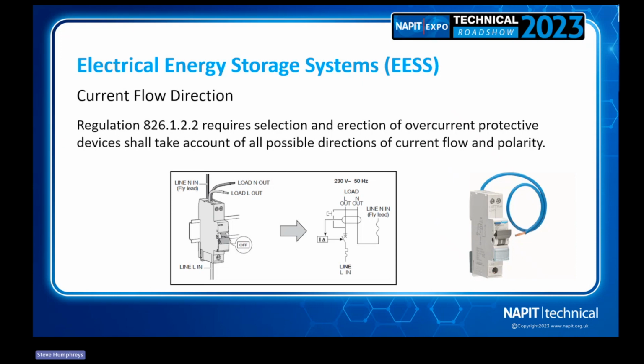Sometimes they could be on the side of the device, sometimes on the front of the device, but if we're feeding energy back in from a local generation, we've got current coming the other way, so we need to ensure that the device is bi-directional. Very important that you speak to manufacturers. We've got a Hager one as an example there. Lots of manufacturers do these bi-directional devices because we don't want to render them useless by feeding current in the wrong way, so they don't work for full protection, additional protection, whatever it may be.